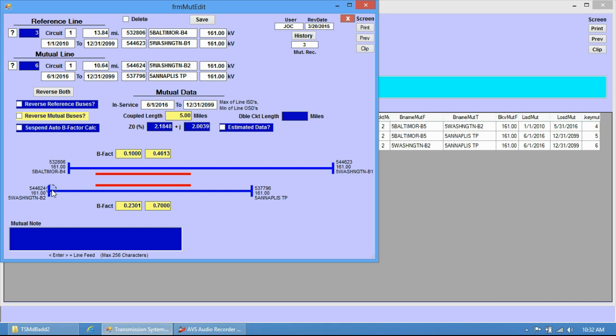Now this is, as I said earlier, a node breaker model, which means that you seldom will have the exact same bus on each end. This is the end of the line, not the bus at the end. But if you do have a bus, then it's the same bus. These two will be tied together with a little piece of drawing, and you'll be able to see that the two buses at that end are the exact same bus, and you can still do all the impedance and B factors.